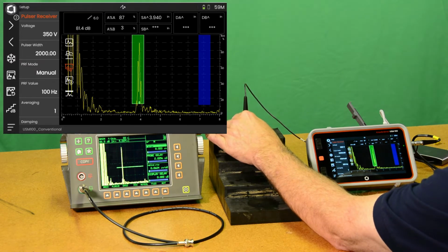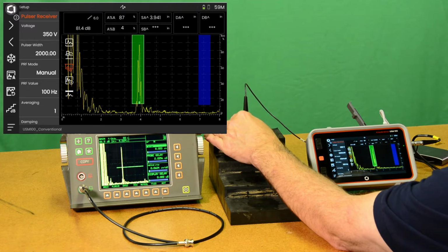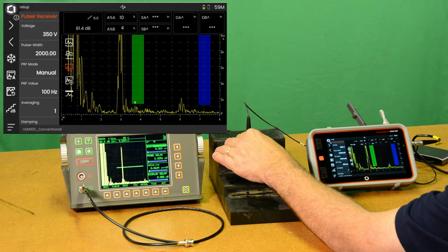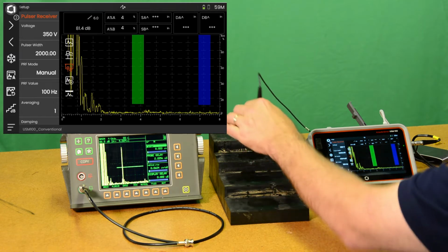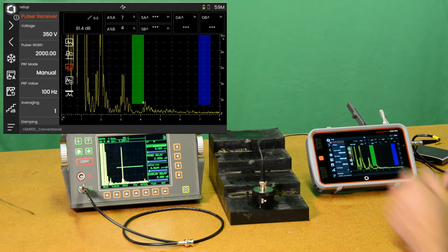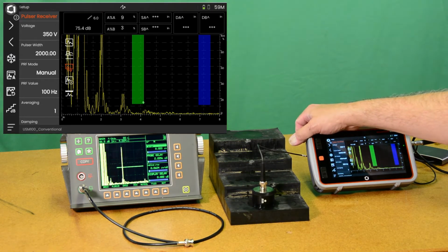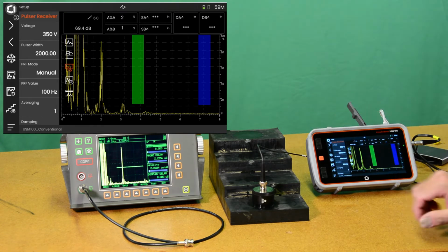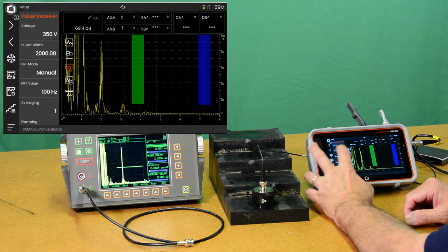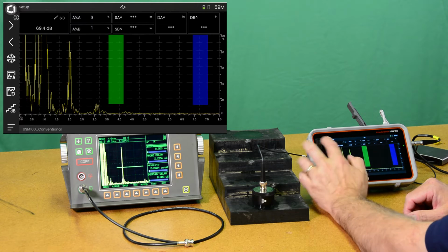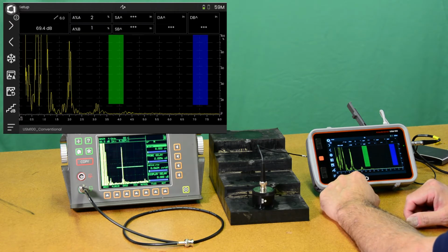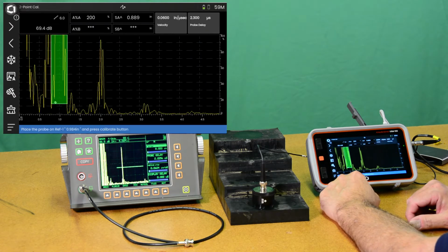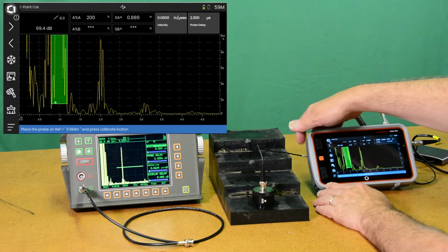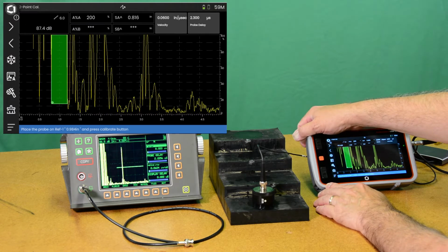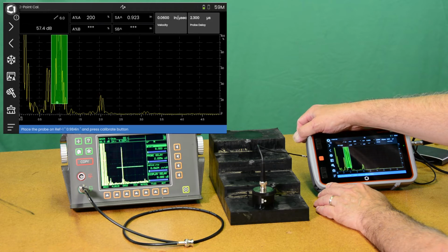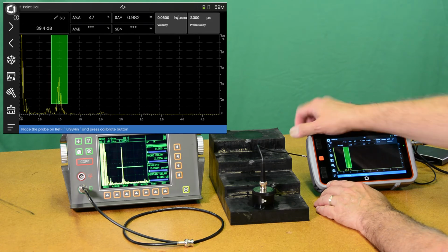Nice quiet noise floor. 3 inches, 2 inches. So now let's take some of that gain out. We'll go back to our 1 and 2 inch steps, and we will advance to the next panel where we can do a 2-point calibration. So we're going to do our calibration at 1 inch and 2 inch. Take our gain down here over our 1 inch.